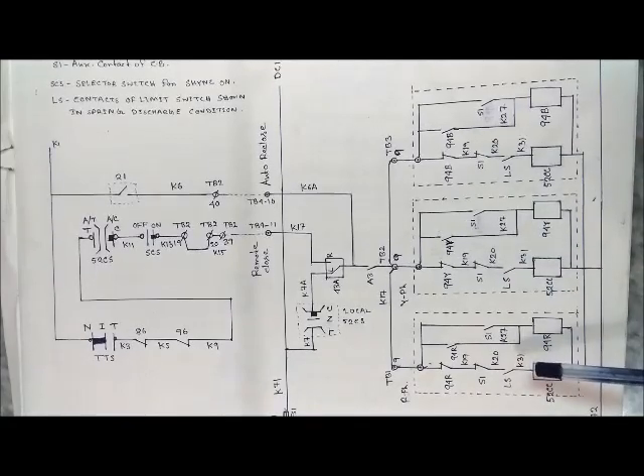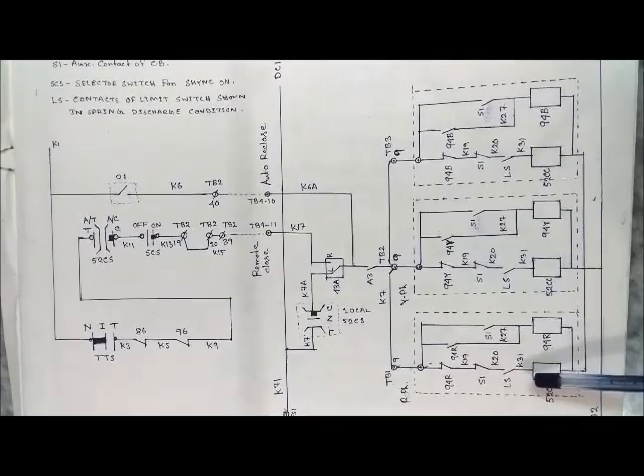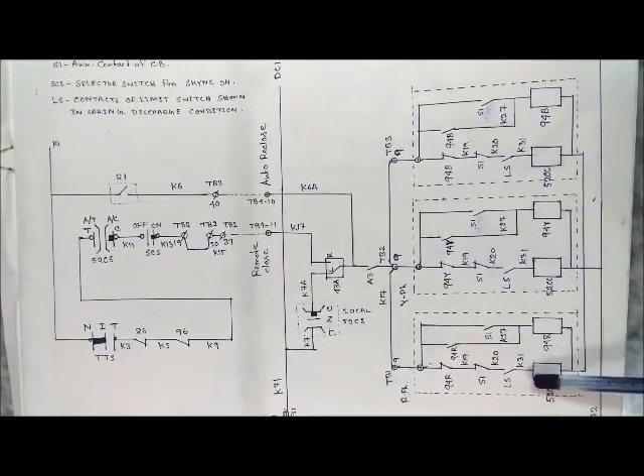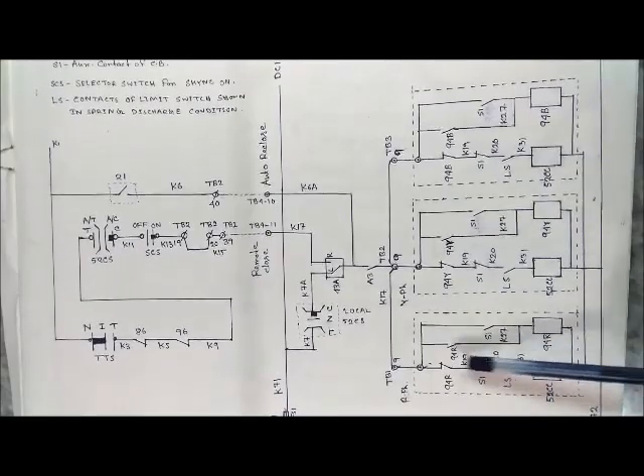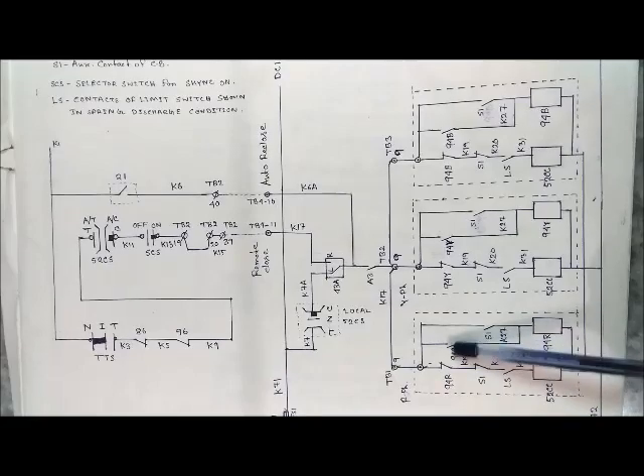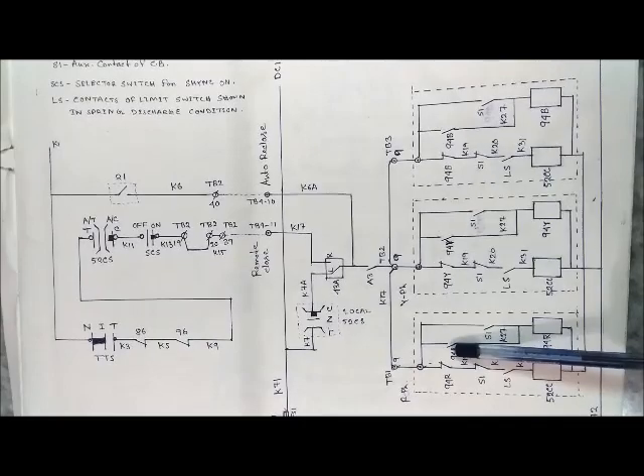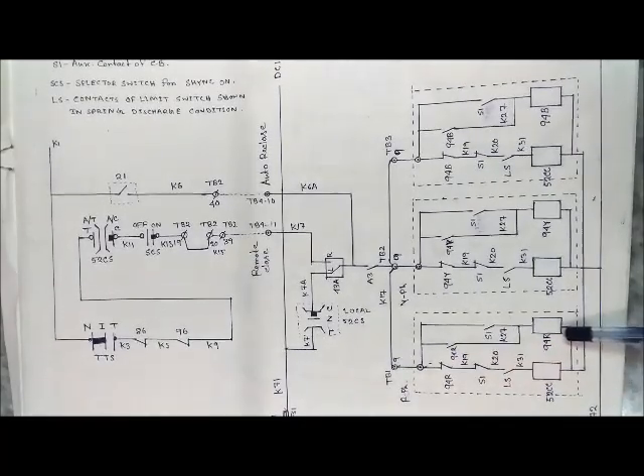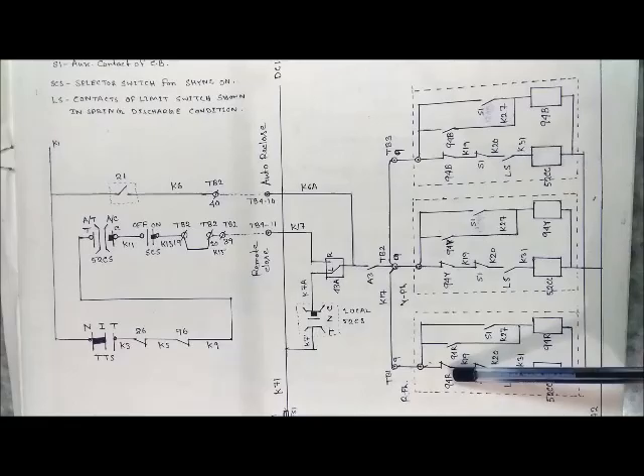S1 is the auxiliary contact of the circuit breaker shown in the breaker-off condition. LS is the contact of the limit switch in spring-discharge condition. If the spring is in charged condition, this contact will be in NC position. 94R are the auxiliary contacts of the anti-pumping relay shown in normal condition. When the anti-pumping relay is energized, the NO contact comes to NC position and the NC contact comes to NO position.